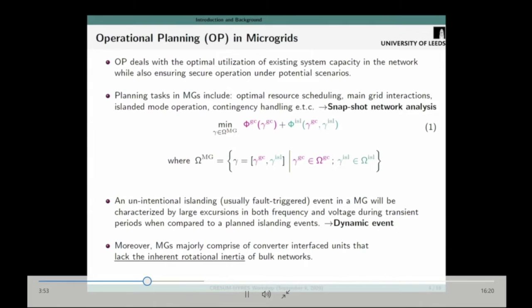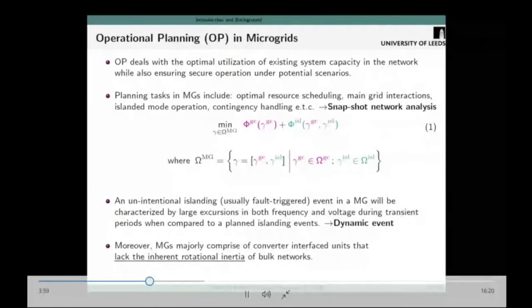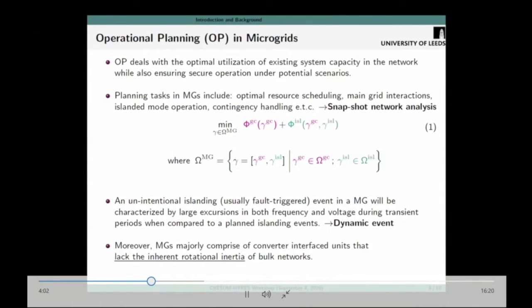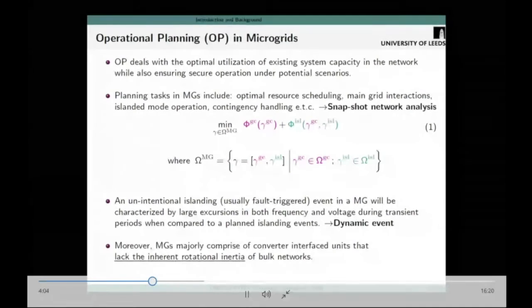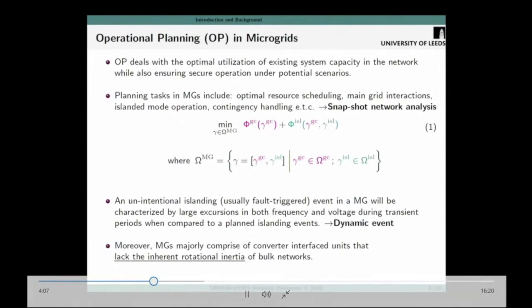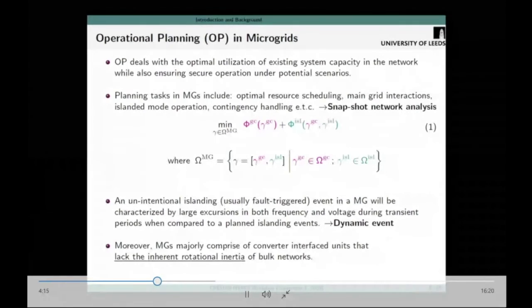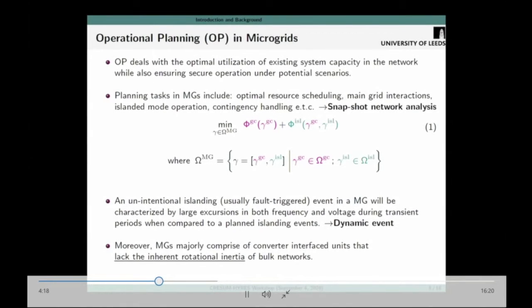When we have an abrupt islanding event of the microgrid, the transient processes are usually characterized by high excursions in both frequency and voltage in the network. And we see that the dynamics of this event will be governed by the different generators that are available in the microgrid. And as we know, microgrids mainly consist of renewable units that are connected through converter interface units. As such, they lack the inherent rotational inertia that's available in the bulk networks that usually contain a high proportion of synchronous machines.